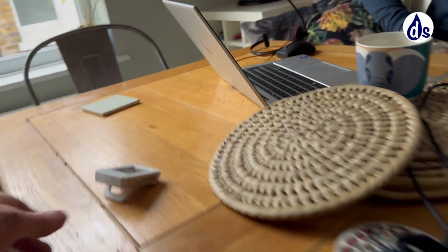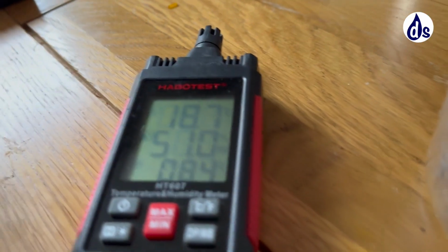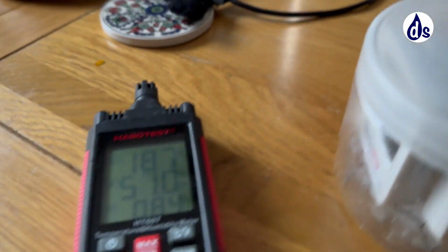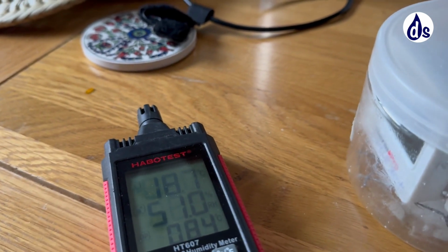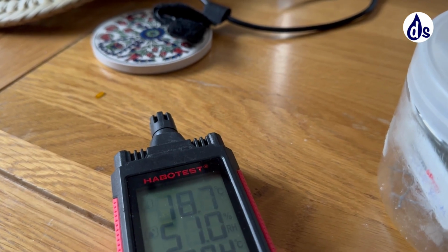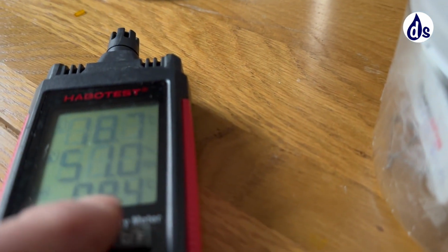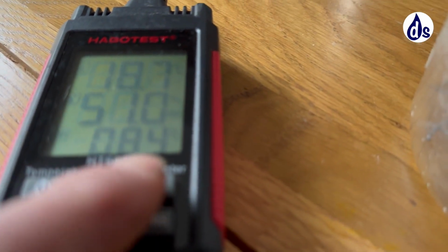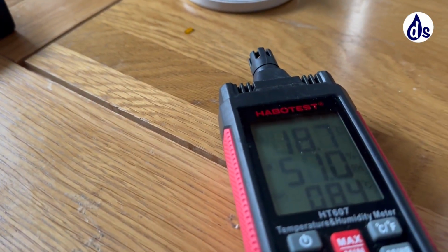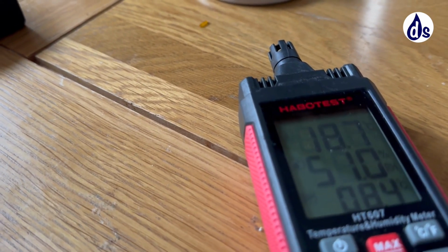And if I look, I've been running a hygrometer. I just switch it on, but it's a tiny size. It's telling me the dew point is 8.4, and mould growth starts when relative humidity goes above 85%. So taking that 3 degree equation, you can work out that the mould point is 8.4 plus 3, which is 11.4, and that wall, I can more or less guarantee you, is below the mould point and therefore at risk of growing mould. And once it's started growing, it will continue to grow.